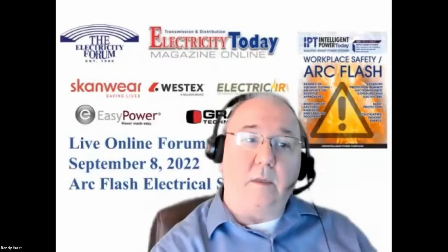Correct. Rather than just relying on PPE to do all the work for you, look at the system and see what can be done to make things safer and reduce the reliance on PPE, or reduce the amount of PPE you need to wear. Can we use Arc Flash mitigation systems, for example, or remote switching operations, to bring that risk right down and protect the wearer?